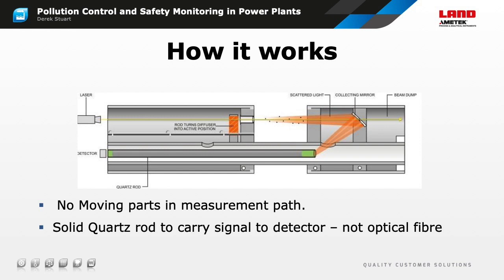Here's a more detailed view of the interaction region of the LAND 4650 PM. You can see the laser beam passing through the interaction region and then passing through a hole in the collection mirror before entering the beam dump. The mirror collects the scattered light and focuses it onto a light pipe which carries it back to an optical detector mounted outside the stack. The light pipe allows us to keep all of the electronics, including the detector, in the cooler area outside the stack, so the only things in the hot environment are passive optical components.